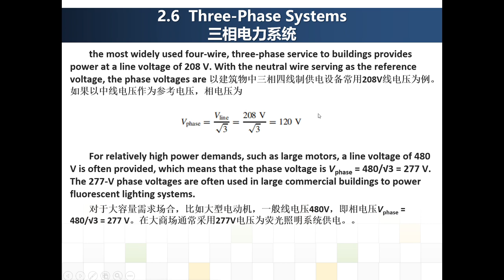The 4-wire 3-phase service to the building provides power with a line voltage of 208 volts. We usually use the line voltage to describe the transmission system or distribution system, and the neutral wire serves as a reference voltage. The phase voltage is 208 divided by square root of 3, which is 120 volts. So we can see the phase voltage is still 120 volts.